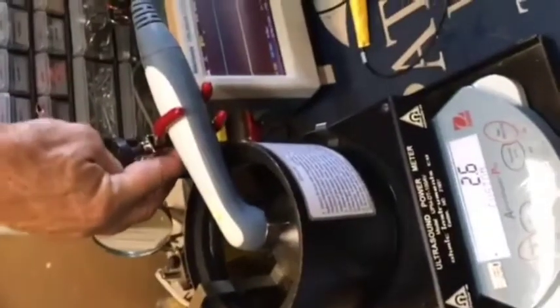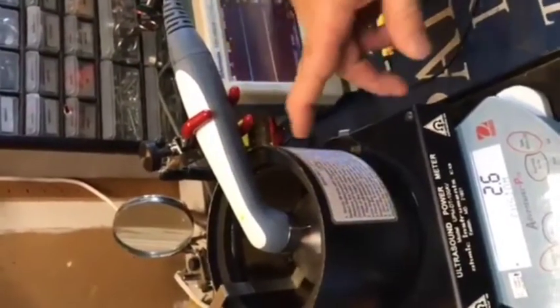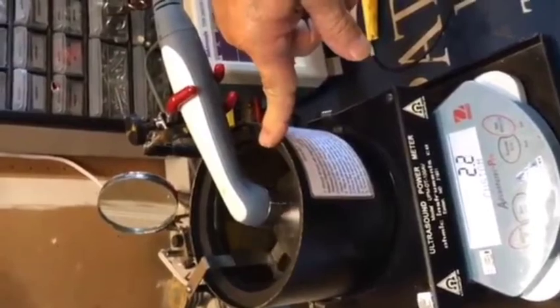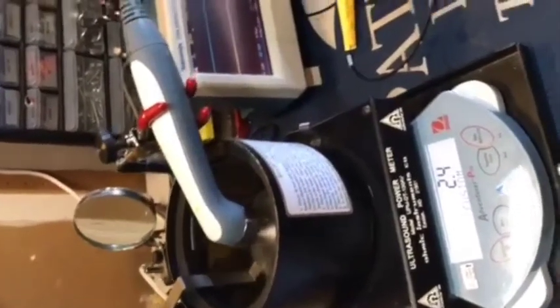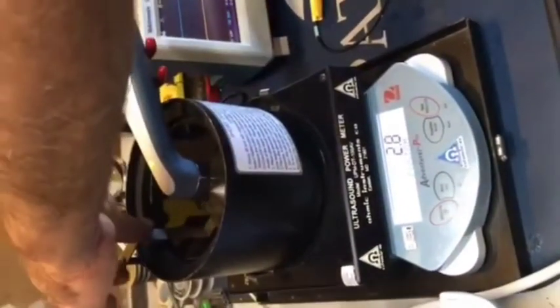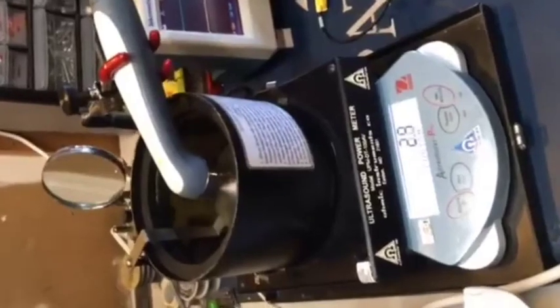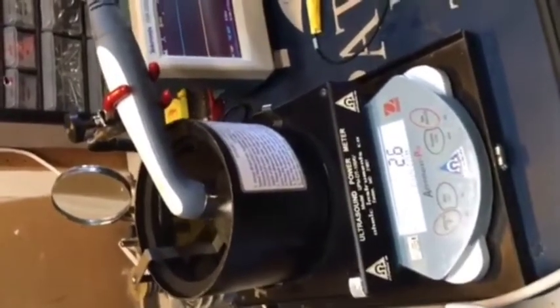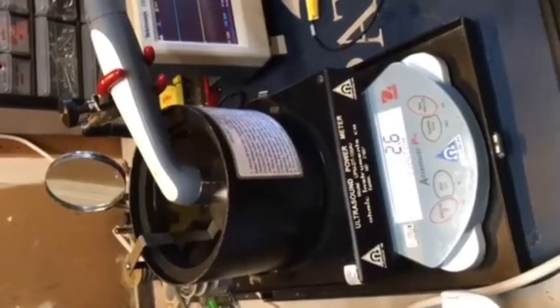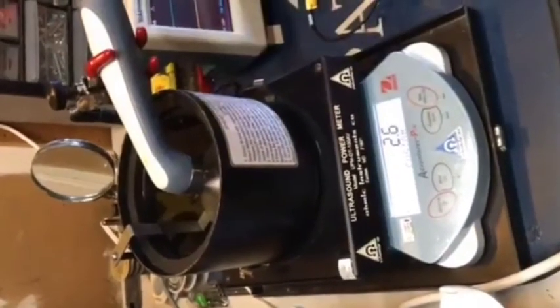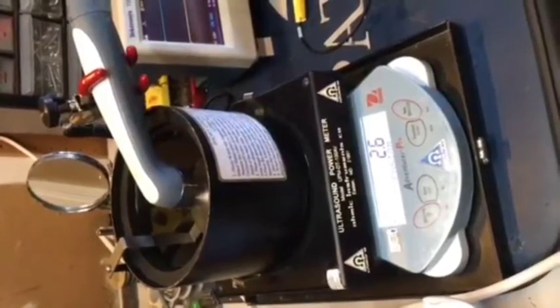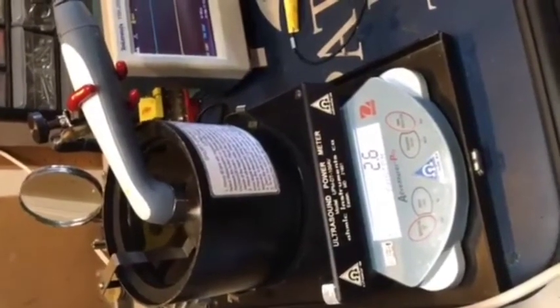The other thing is that a lot of times the sound head or the holder is pressing down on this. You'll see if you press down on it, it's going to change. Sometimes that happens. So there's stuff to do before you freak out and say it doesn't work. And if all that seems to be in place, and none of those things are interfering, you've got a calibration issue. And I will show you how to calibrate this machine.